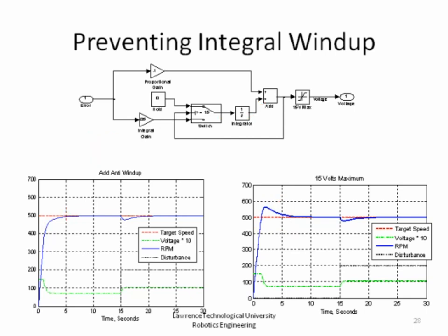And in other applications, you could even get instability and oscillations because the controller winds up one way, even though it can't really do anything. And it's wound up so far when you're on the other side of the set point, it has to unwind. But by the time it unwinds, it's gone too far. And you can drive instability or oscillations due to this windup. Not a good thing. So any time you have an integrator, you really need to include some anti-windup.